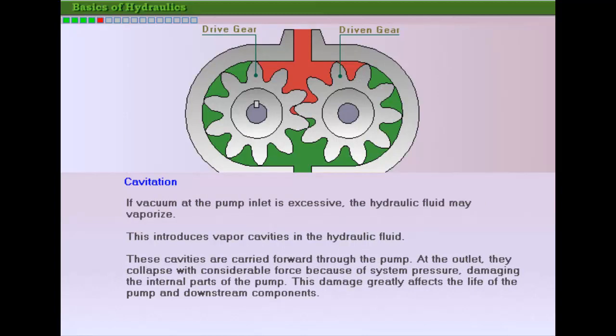Cavitation is a common problem which occurs in pumps due to excessive inlet vacuum. Very high inlet vacuum may vaporize the hydraulic fluid. These vapor cavities are carried inside the pump to the outlet and collapse with considerable force when exposed to outlet pressure.